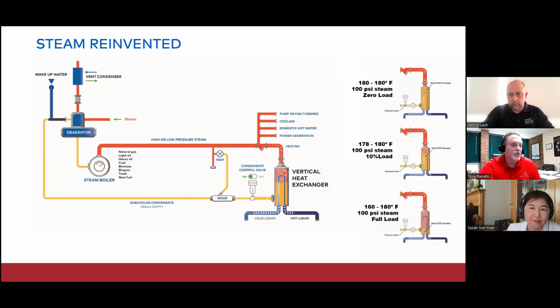By doing this, we now have high pressure steam coming in. We have that ability now to push condensate without using a pump all the way back to the deaerator or boiler feed system. This allows us to have zero air infiltration in our system and eliminate all of those flash losses that you can associate with a traditional system.